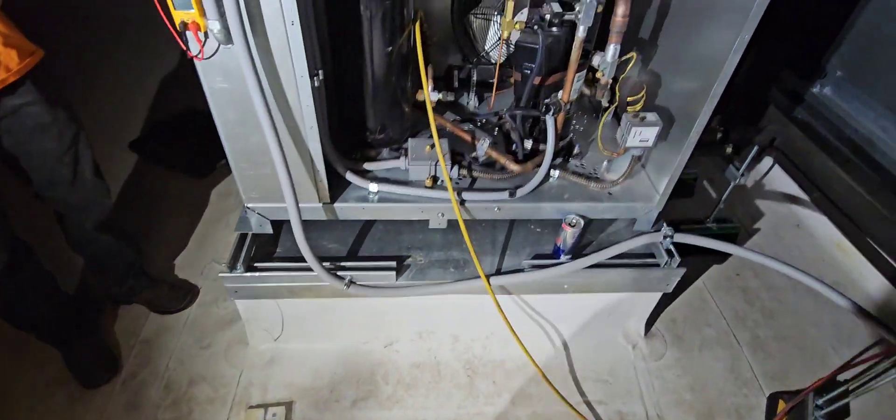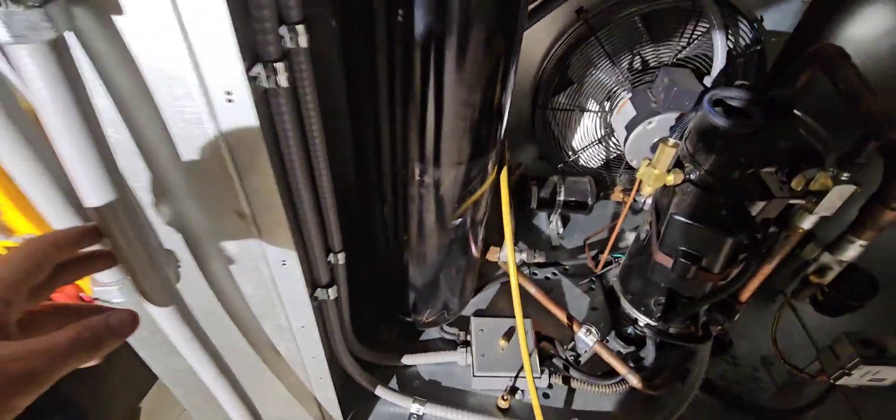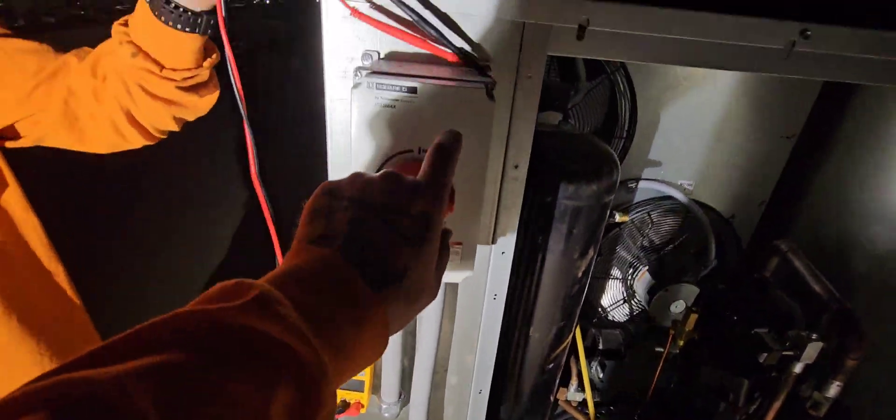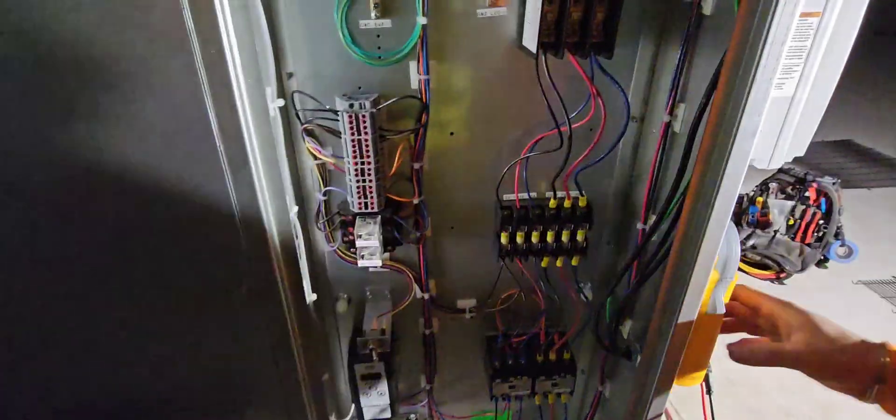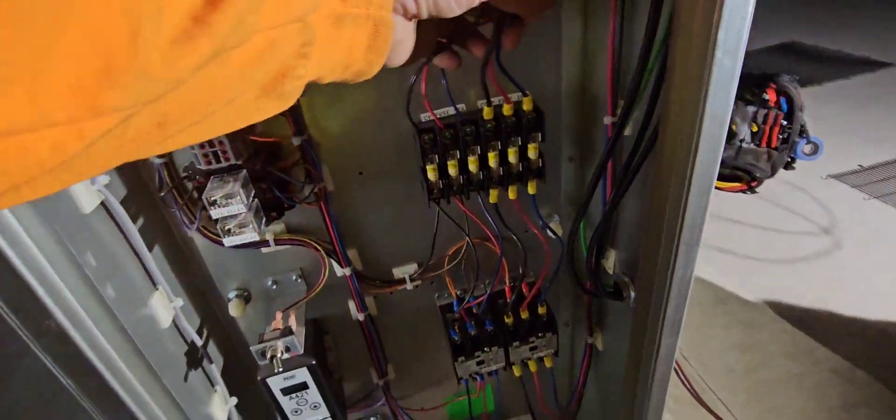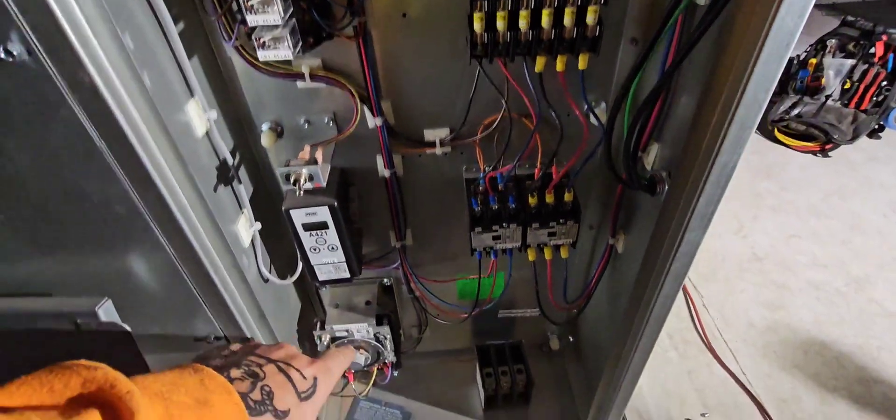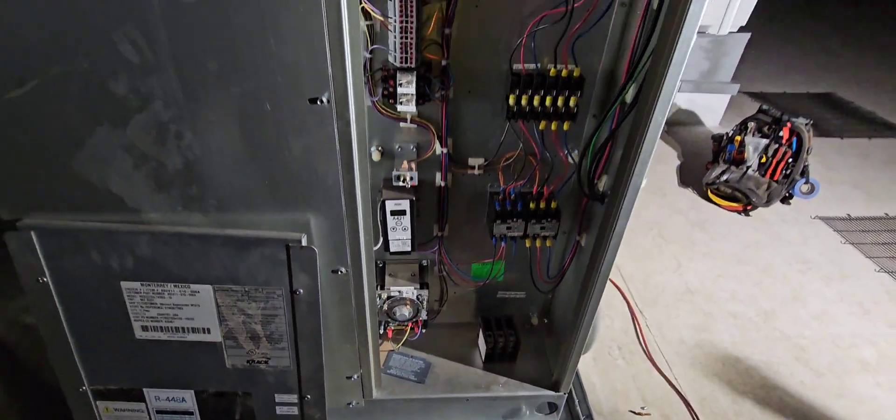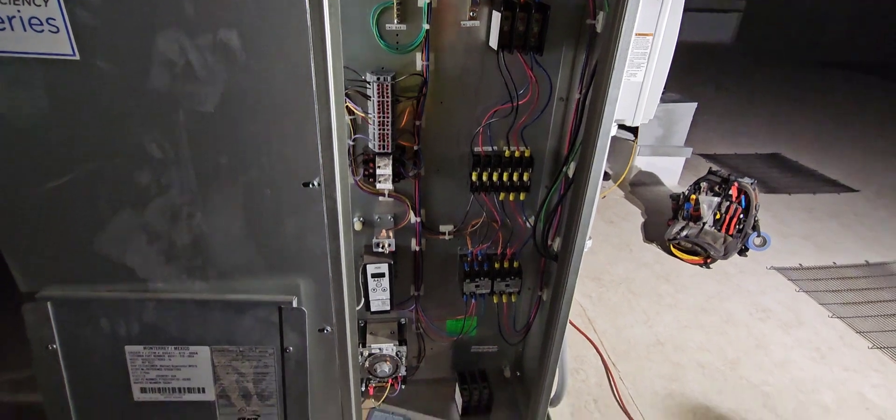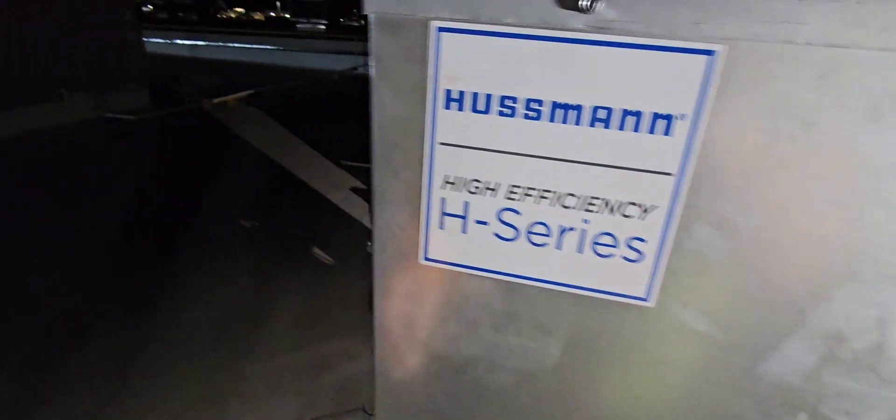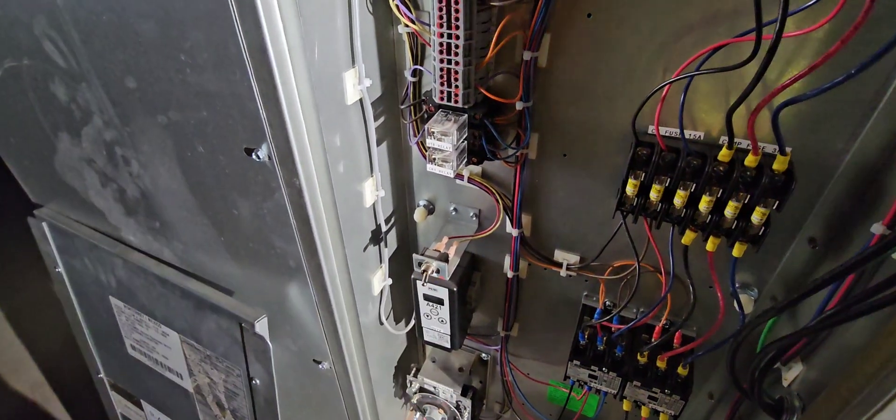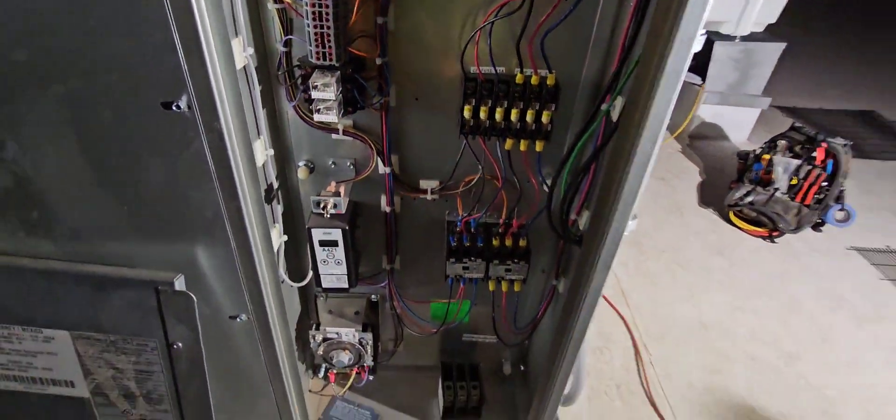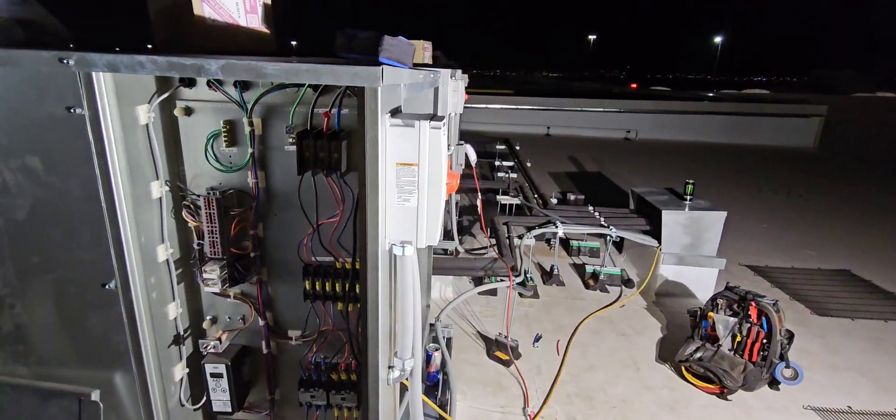The electricians landed everything for us, all the breakers should be on. First thing I'm going to do is open this up, check power, and then we'll check phase in here. Nothing should run yet because everything's off the KE2s that are down below. This fan cycle switch has a sensor that'll cycle one of those fans. This pump down switch isn't really in play, all the controls are based off the KE2.